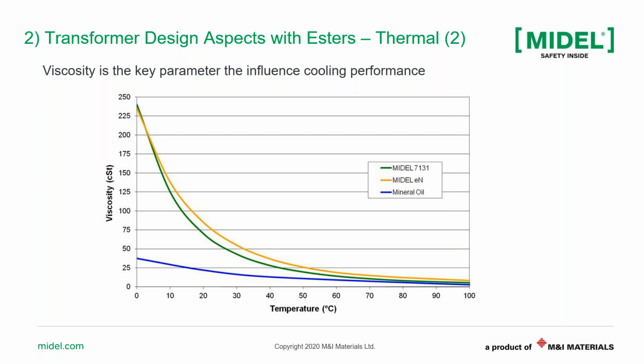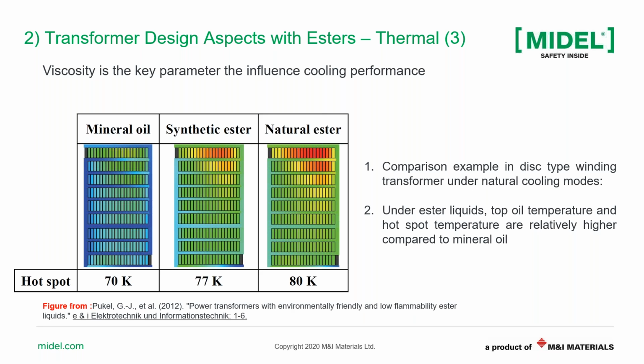And to give more understanding on the liquid, if we focus more, the main parameter that contributes to the cooling ability of the liquid is the viscosity. Esters are known to have higher viscosity than mineral oil, and this is actually the reason why they have a high fire point. So they are fire safer, K-class. But as you can see, it depends where you are operating. Above 60 degrees, the difference in viscosity between esters and mineral oil is reduced. But for cold start, we need to take more precautions, either in our transformer design or operation, to deal with that. But to give more numbers now, instead of talking in general, let me share with you some published cases for simulation to show.